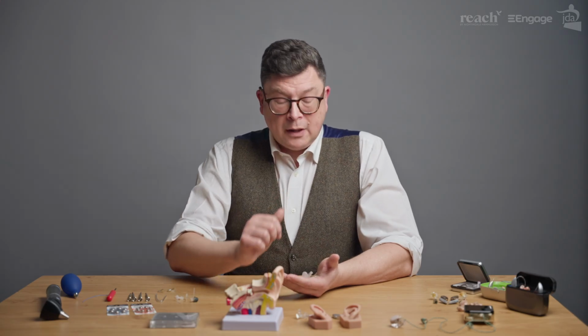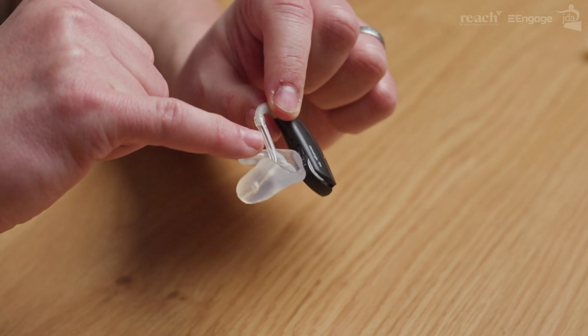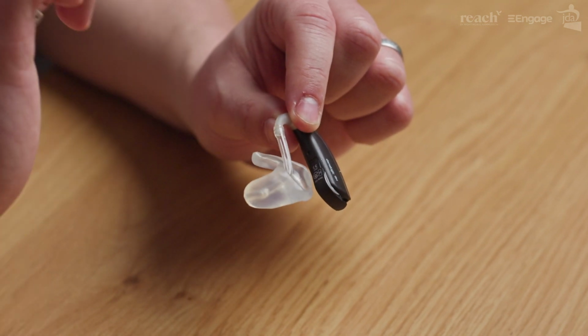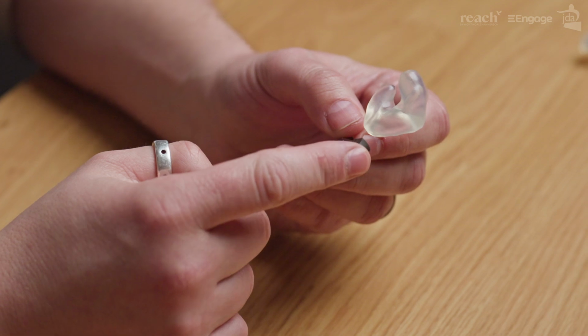There we go. If the hearing aid doesn't make a noise, check if the tubing is blocked with wax. If it's clear, change the batteries and try again. If the hearing aid still doesn't work, then it may be faulty and will need to be returned to where it came from to be fixed.